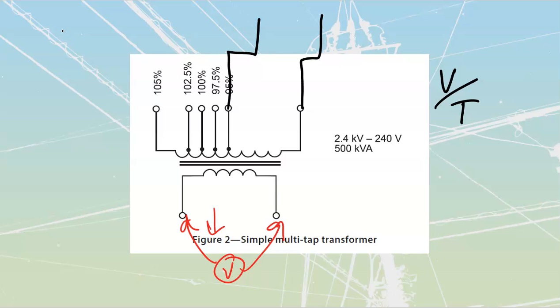If they do have the plant millwright making those adjustments, they'll want to place on a tap changer. Now, an on-load tap changer is able to change the taps while the load is still on. They don't need to go into a shutdown. A no-load tap changer is cheaper, smaller, easier to work with, but you have to shut everything down, click it over to the next position, and then turn that back on. If you don't have one of those tap changers, the only other method would be to actually open up the transformer and select and clean off the high voltage taps.